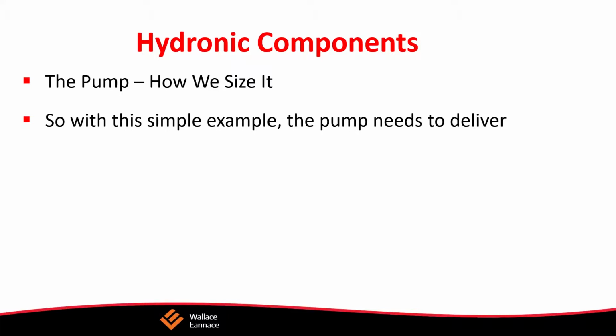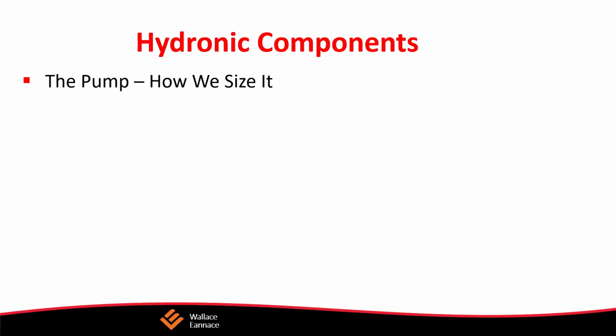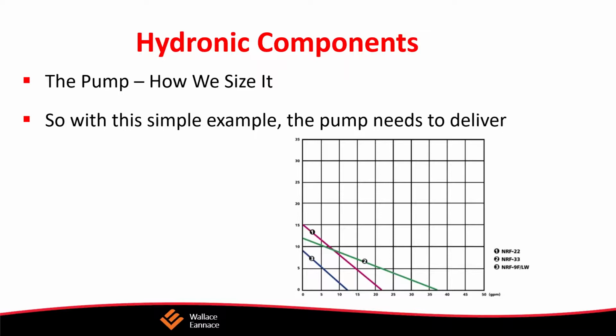Let me go back a little bit. Take a look at hydronic components. The pump. When we're looking to size a pump, there are two components. The BTUs tell us the amount of flow that we said before. We took the amount of BTUs divided by 10,000 on a 20-degree delta T, and that told us the flow. If we have a newer condensing system, we may want to use 30,000 BTUs. We may want to divide by 30-degree delta T. We may want to divide by 15,000.